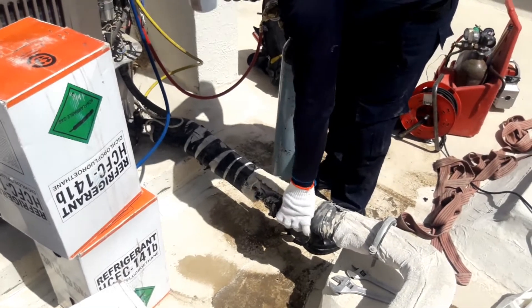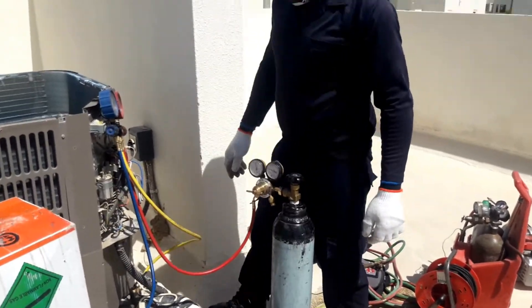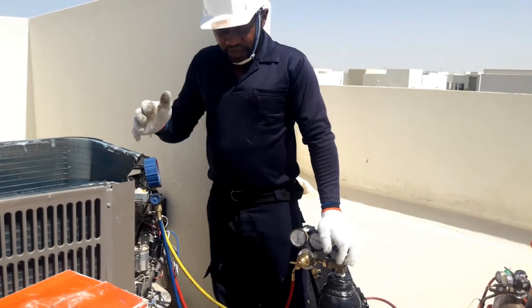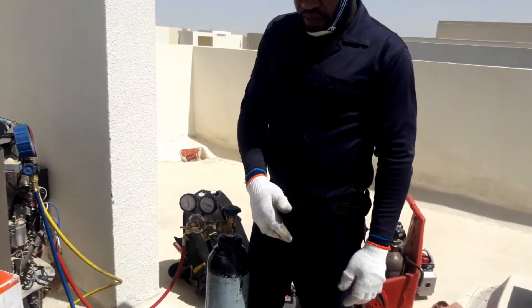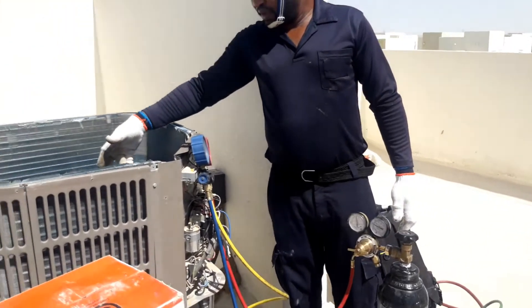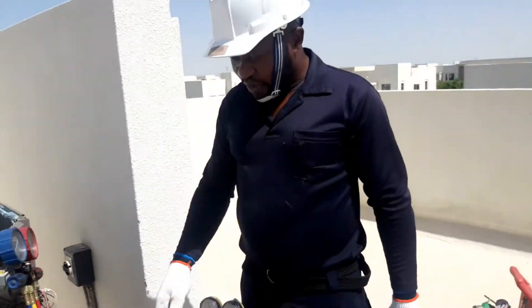What's next: we just replace the filter with a new one, make a new connection, open here, vacuum the system, and fill refrigerant in the system. So this is how to flush the indoor unit without removing the compressor. You can see the compressor is here — we did not disconnect it, we just flushed the indoor unit from outside.